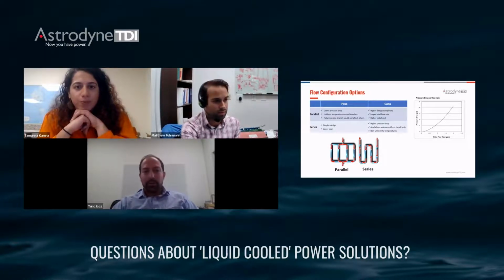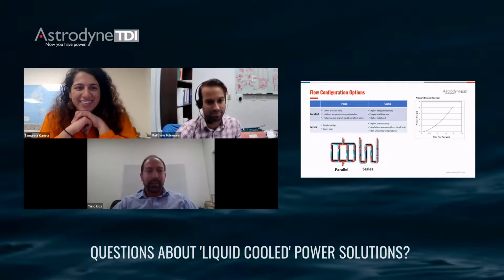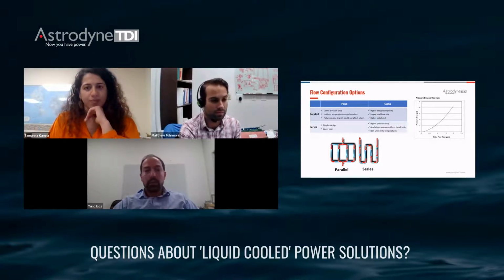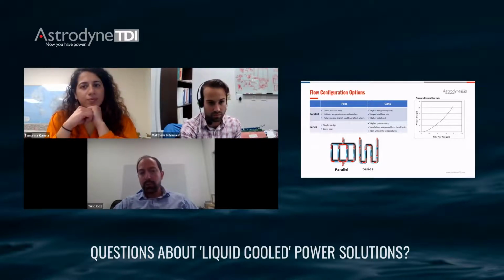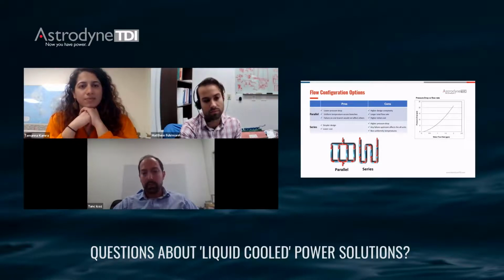Yeah, so this is the fun part, in my opinion, of this problem, solving a puzzle here. So there are 2 main configurations. One can argue that hybrid is a third option, which is obviously very true. But let's talk about the 2 main ones. So parallel configuration is where there's a main incoming flow. There's a manifold before the units that are being cooled, and the manifold distributes the incoming flow into different branches, and then there is a secondary manifold at the exit that collects all the flow from every branch, and then takes it to the heat exchanger, radiator, whatever the means to reject the heat out of the system.